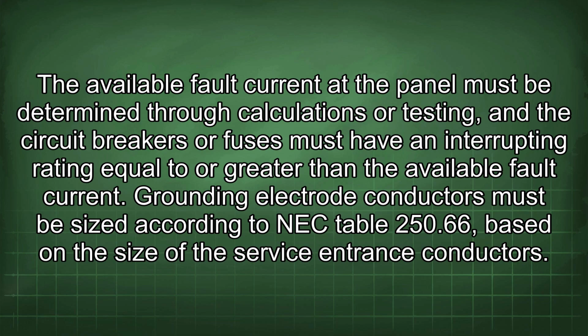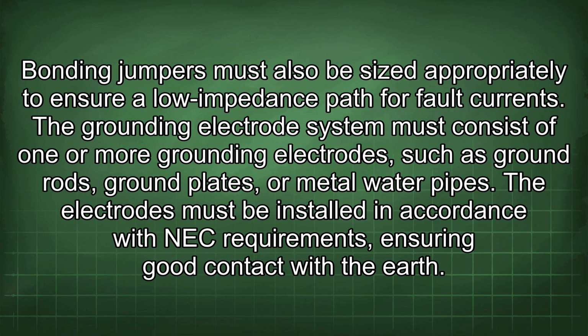Grounding electrode conductors must be sized according to NEC Table 250.66 based on the size of the service entrance conductors. Bonding jumpers must also be sized appropriately to ensure a lower impedance path for fault currents. The grounding electrode system must consist of one or more grounding electrodes, such as ground rods, ground plates, or metal water pipes. The electrodes must be installed in accordance with NEC requirements, ensuring good contact with the earth.